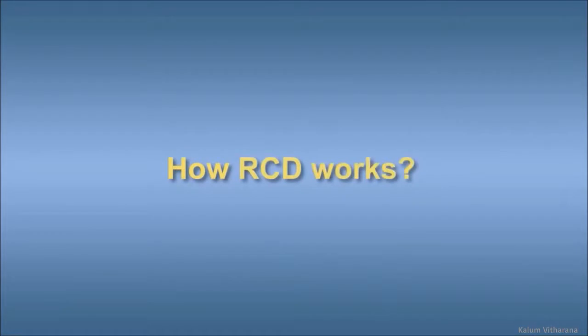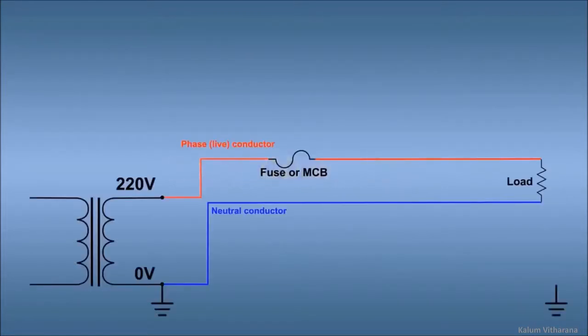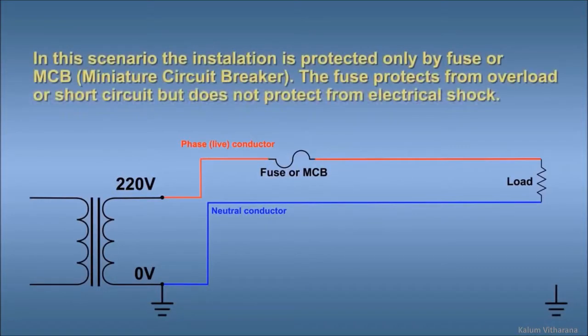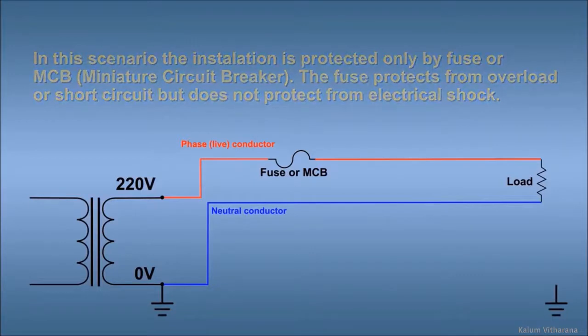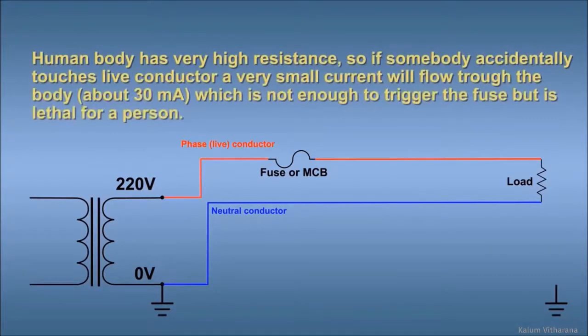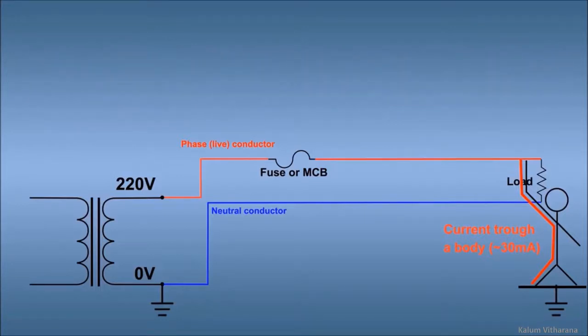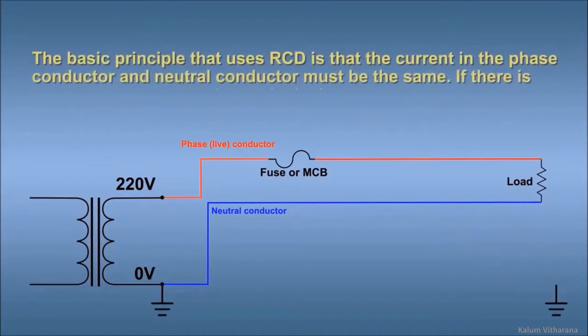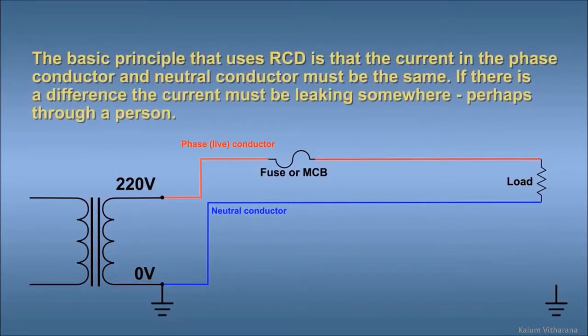How RCD works. In this scenario, the installation is protected only by a fuse or MCB, miniature circuit breaker. A fuse protects from overload or short circuit but does not protect from electrical shock. The human body has very high resistance, so if somebody accidentally touches a live conductor, a very small current will flow through the body, about 30 mA. That is not enough to trigger a fuse but is lethal for a person. The basic principle that RCD uses is that current in the phase conductor and neutral conductor must be the same. If there is a difference, the current must be leaking somewhere, perhaps through a person.